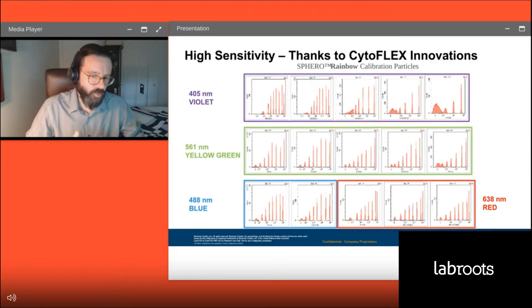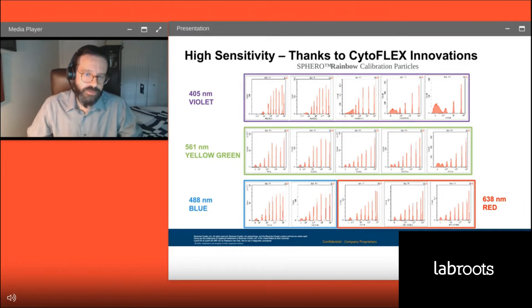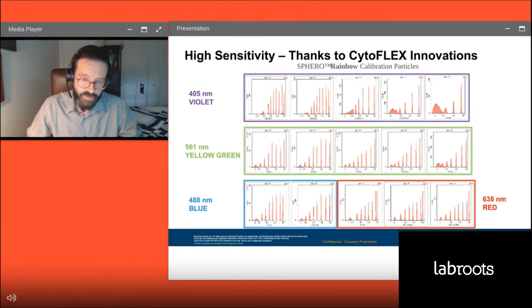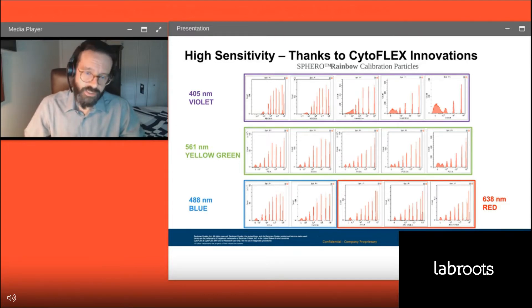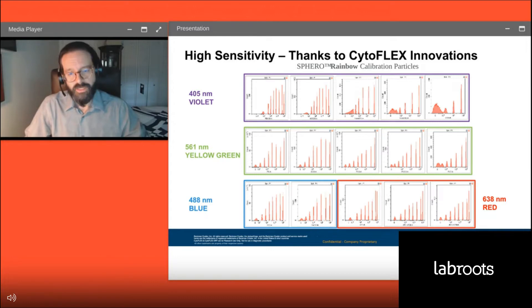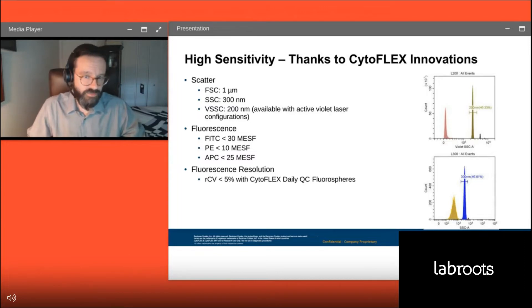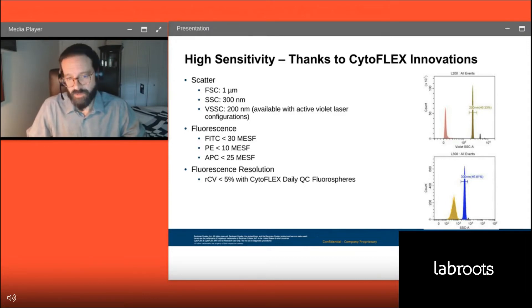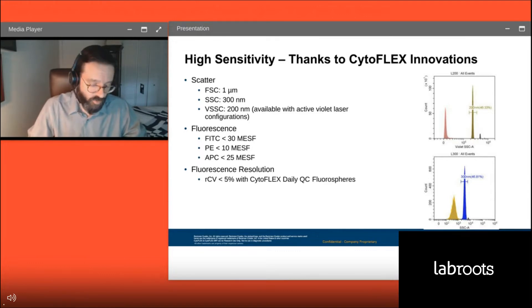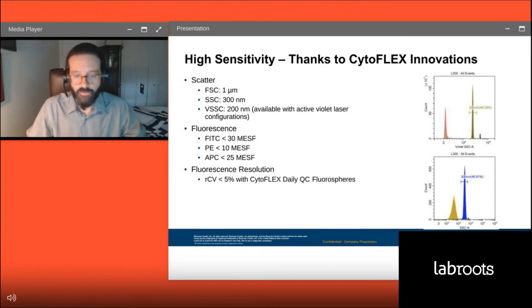One important thing to highlight is the high sensitivity the CytoFLEX analyzers are known for — we've carried that over into the CytoFLEX SRT cell sorter. With eight-peak Spherotech beads as our standard, we're able to see all eight peaks in the majority of channels, except in some longer Stokes-shift parameters in the violet laser. We've also carried that sensitivity over into scatter with violet side scatter — detecting up to 200-nanometer polystyrene particles, allowing us to sort very small nanoscale particles with high fluorescence sensitivity due to the avalanche photodiode detection systems.